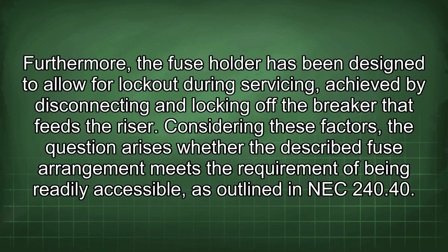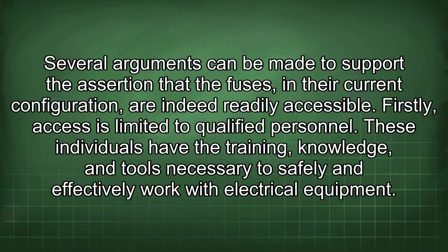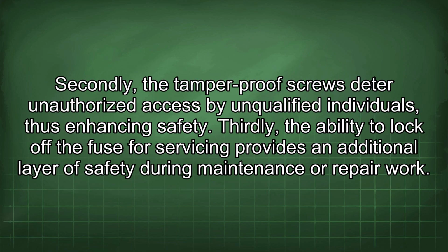in NEC 240.40. Several arguments can be made to support the assertion that the fuses, in their current configuration, are indeed readily accessible. Firstly, access is limited to qualified personnel. These individuals have the training, knowledge, and tools necessary to safely and effectively work with electrical equipment. Secondly, the tamper-proof screws deter unauthorized access by unqualified individuals, thus enhancing safety.